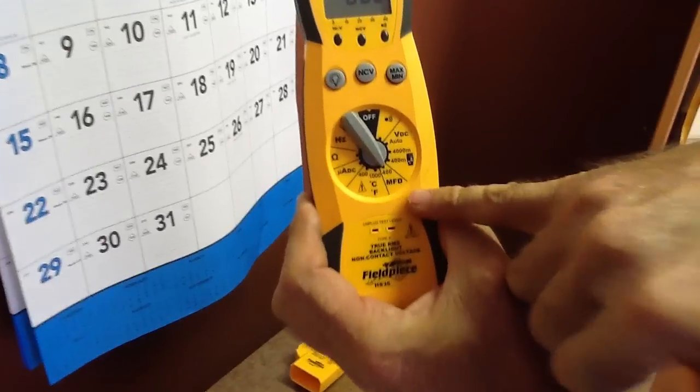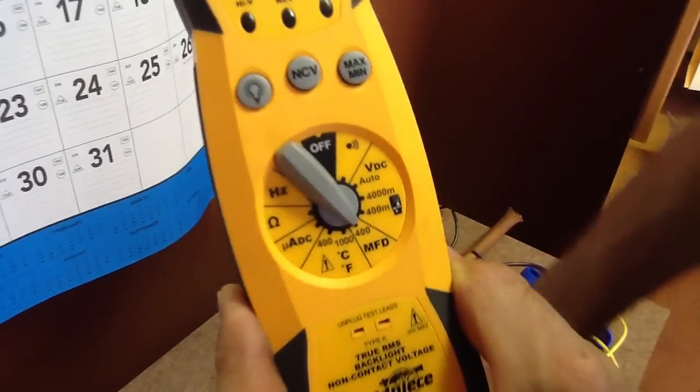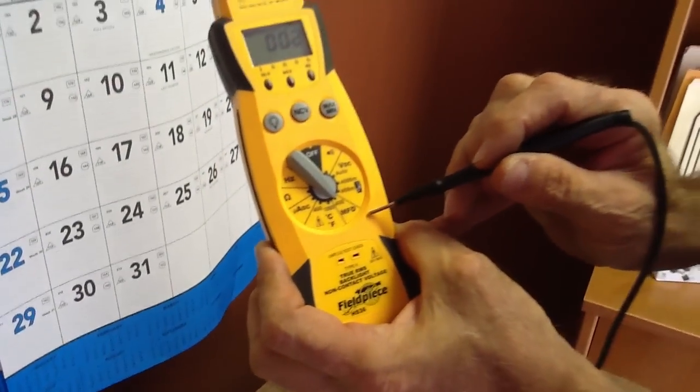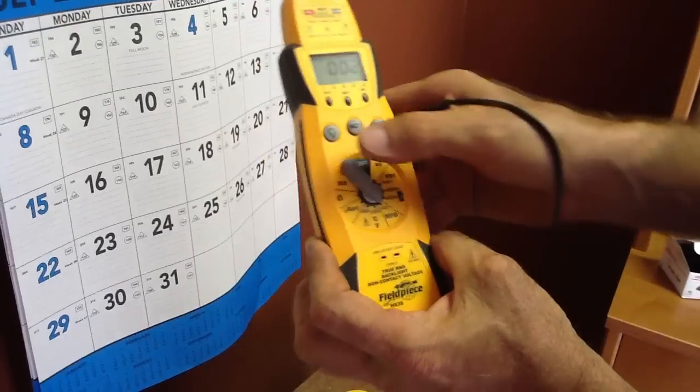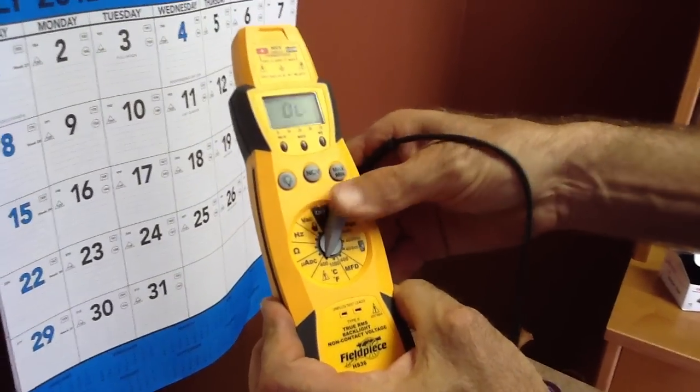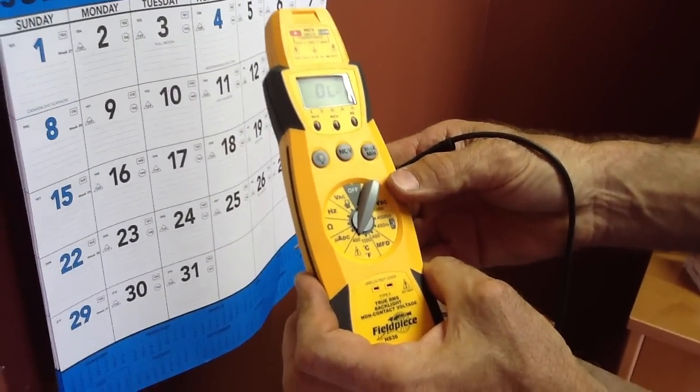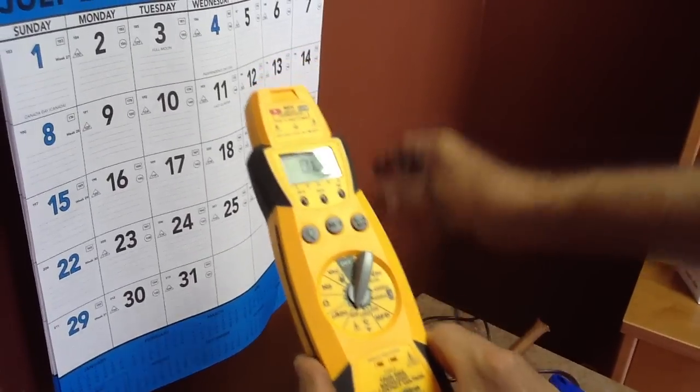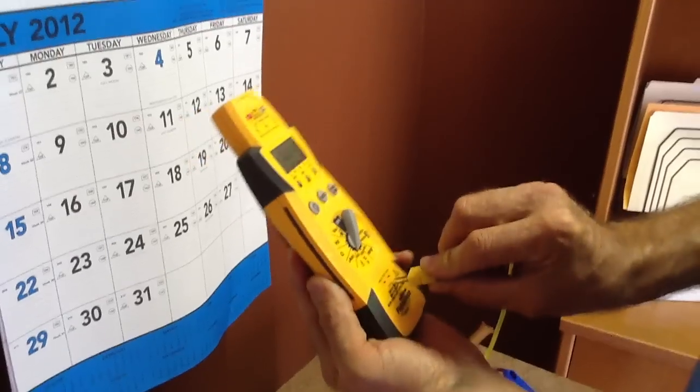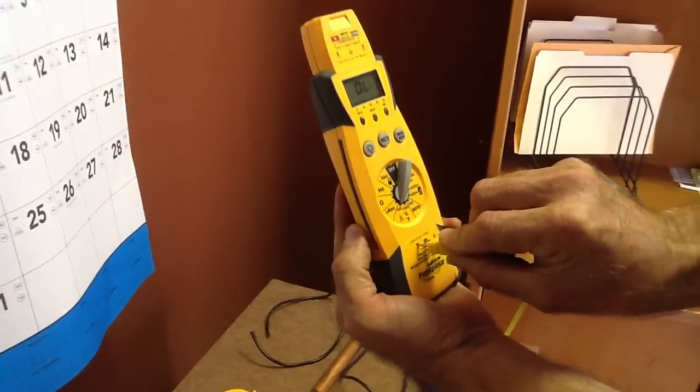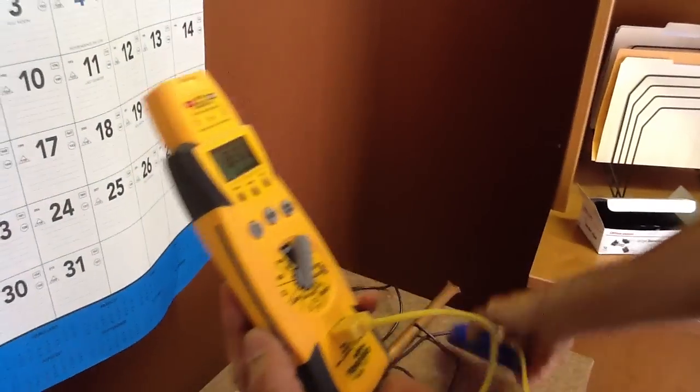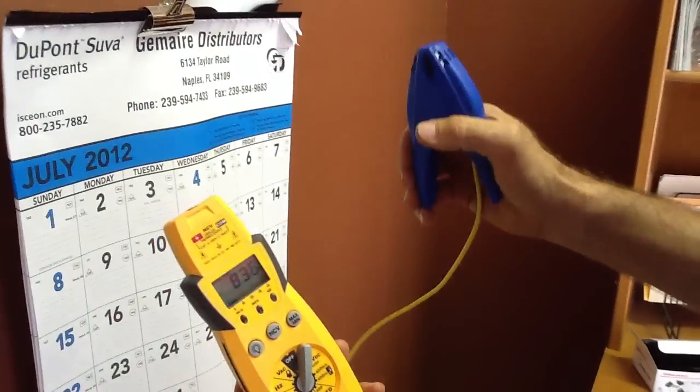Microfarads MFD, you check your capacitors with that, anywhere from 5 to 80 microfarads. It goes up to 400. Temperature probe, you have 400 degrees to a thousand degrees. Okay, so I'm going to put it on 400 for now. You take your temperature probe, you're going to plug it in right here.